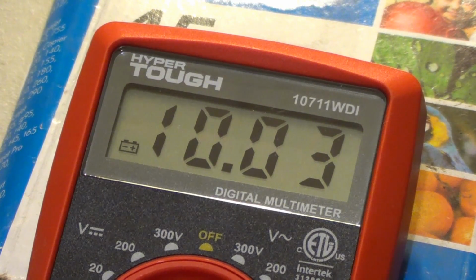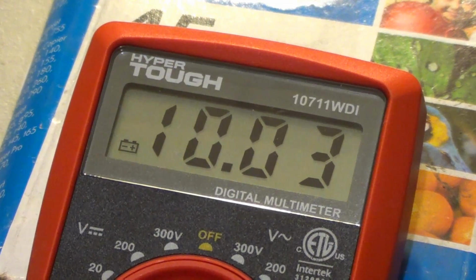Now, it is worth mentioning that just because the meter is indicating accurately on DC voltage right now does not mean that it would indicate accurately on other testing ranges, especially those like the diode test that require more current to operate correctly. So when your multimeter tells you that a low battery issue exists, you should always replace the battery straight away.